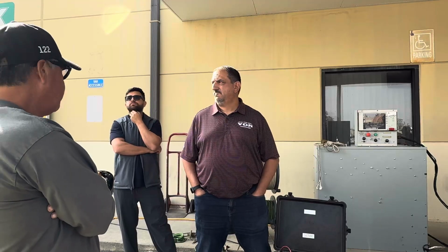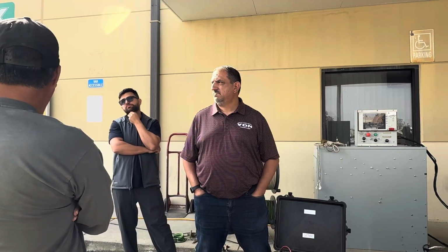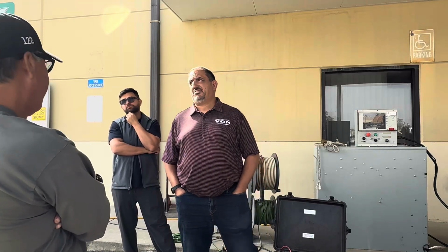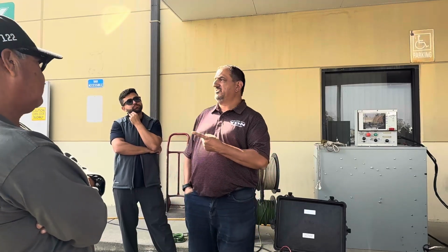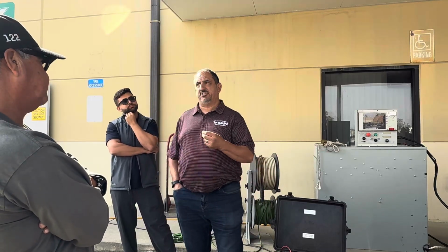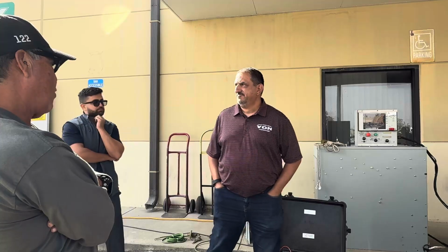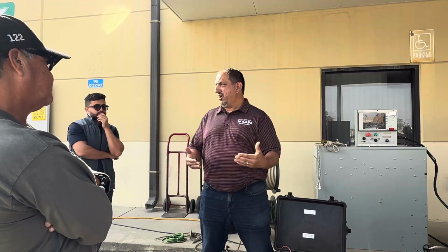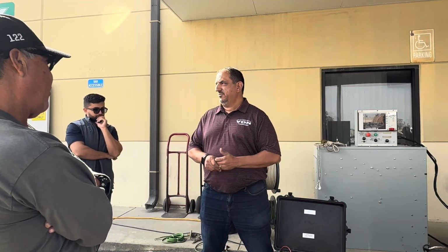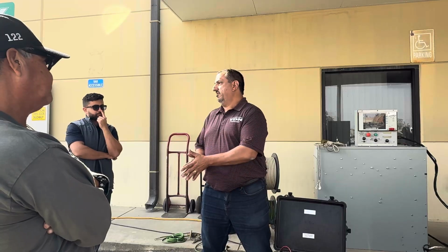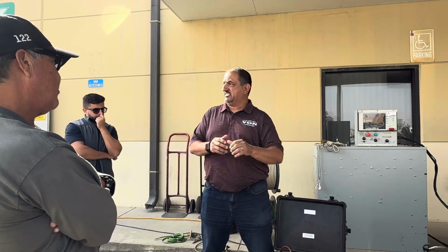If you had that same situation, what's creating that when it's snapping right there? Bad connection? One, it's a bad connection. Two, it's just compromised neutrals. This goes back to when we talked about the hookup: control what we can control. You can control your hookup, make sure it's clean, solid, and tight.